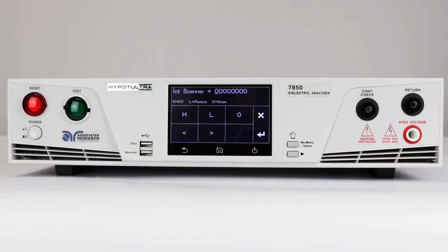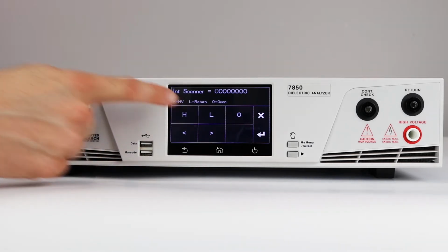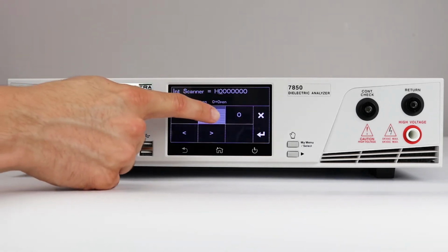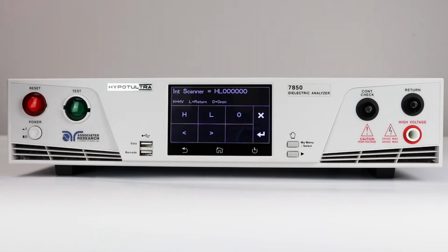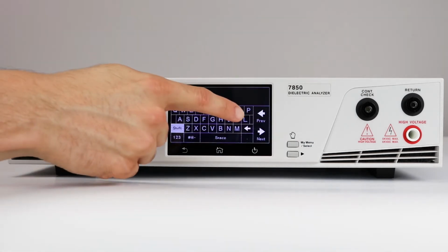Select the internal scanner. Use the left and right arrows to change the scanner channel. For each channel, select either H, which sets the channel to high voltage, L, which sets the channel to return, or O, which sets the channel to open. For this demonstration, we will set channel 1 to high and channel 2 to low. Once all parameters have been input, press the Perform Test icon.